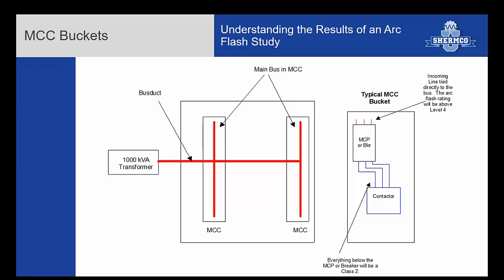If the task is to troubleshoot overloads, even though these buckets are labeled dangerous, if the worker knows not to do anything to disrupt or get under the covers of the line side, they're only going to work and troubleshoot the bucket. Procedures might be enough to allow them to do their task. If they're going to actually need to rack off and on the MCC bucket, well, that's a whole different item.